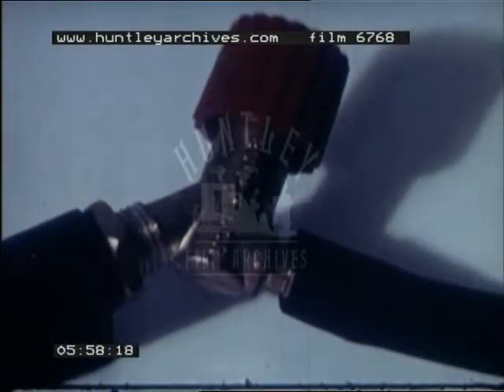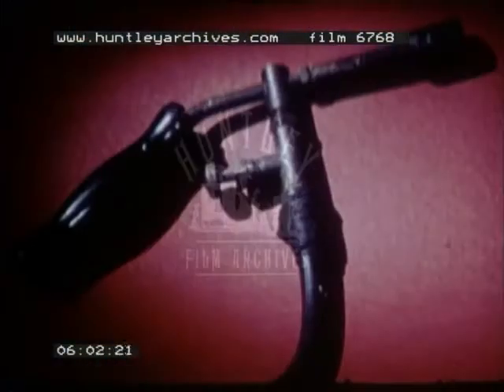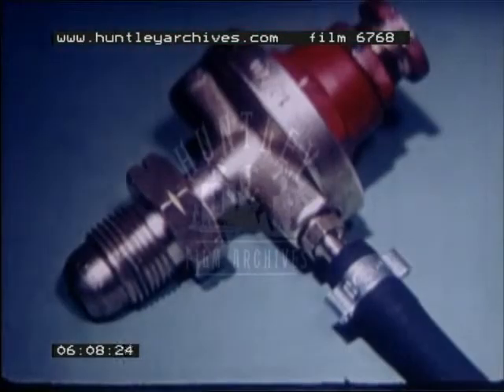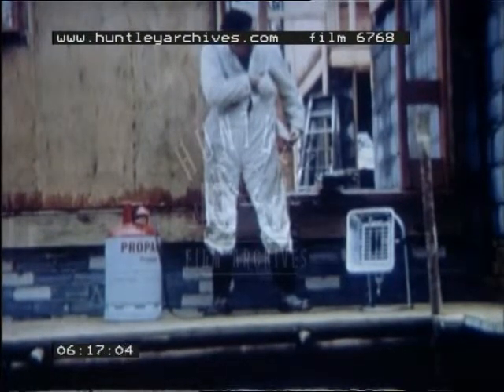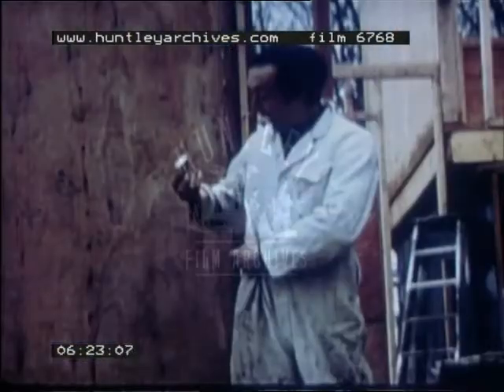When connecting up hoses to the regulator and the appliance, do not rely on a push-on fit or a Heath Robinson effort. These can all too easily come adrift. Always use some form of hose clip. Before turning the gas valve on, have a means of ignition ready and waiting. Unlike this fellow, in the time it takes him to search through three or four pockets for a box of matches, quite enough gas can escape to cause...